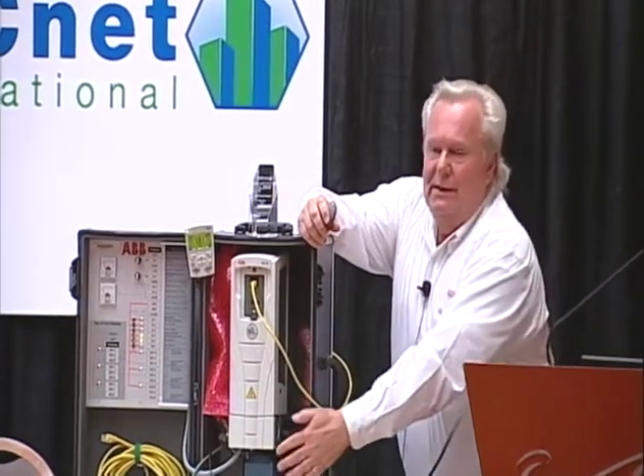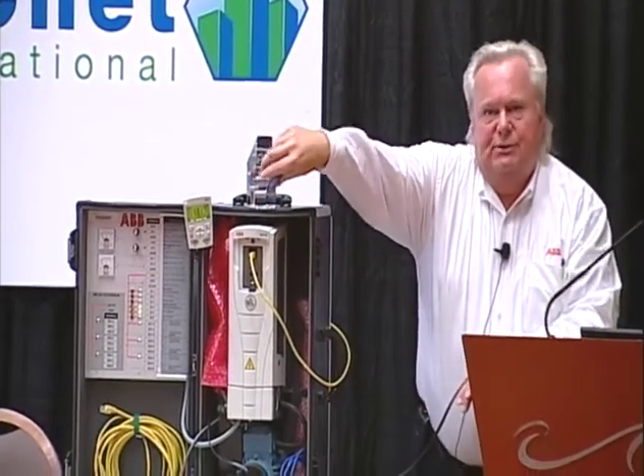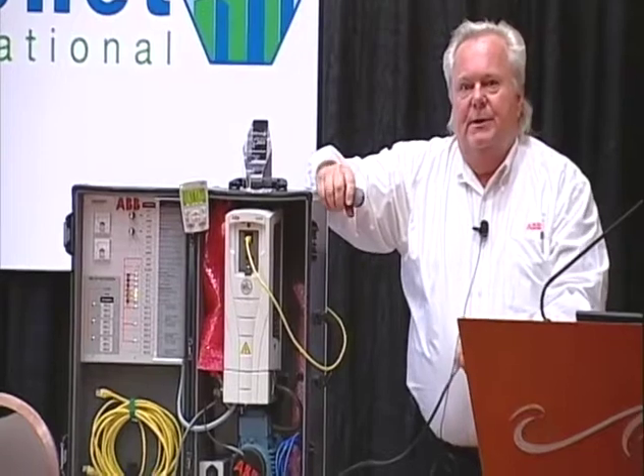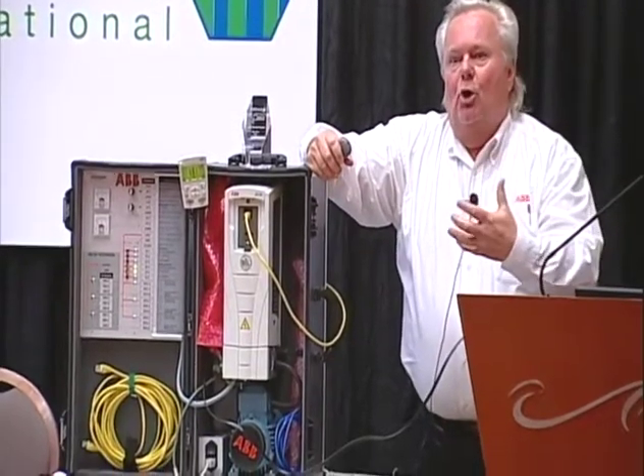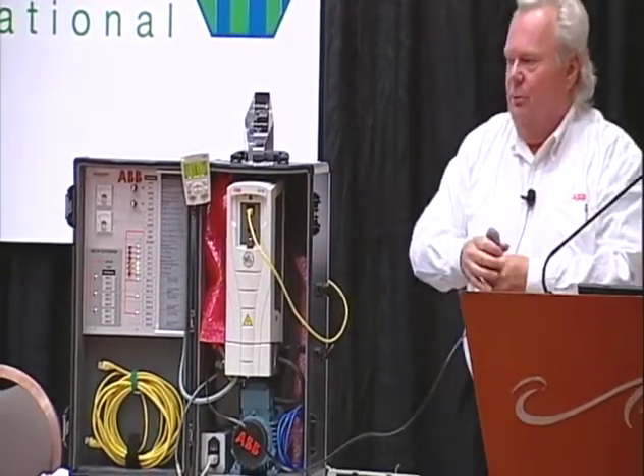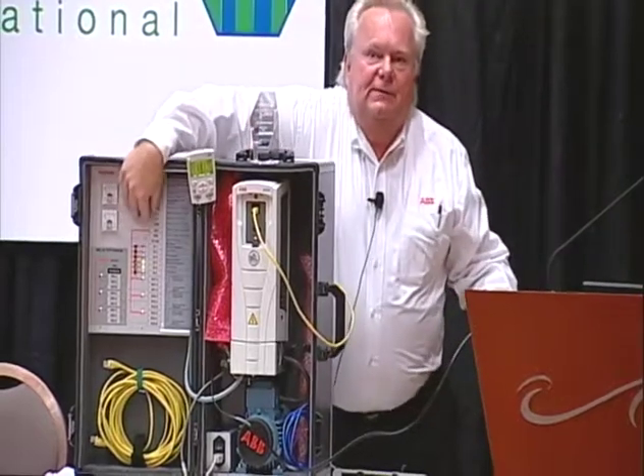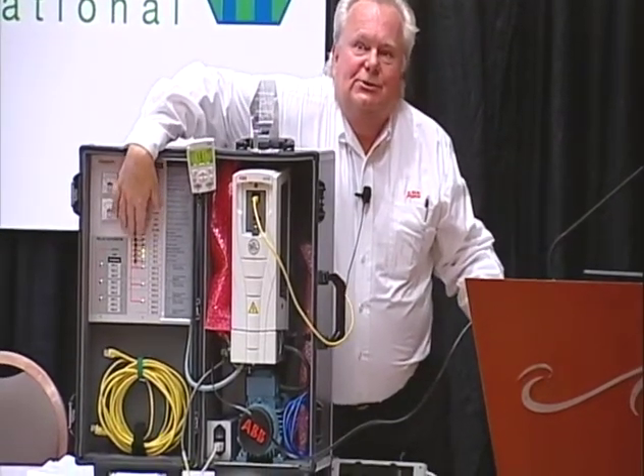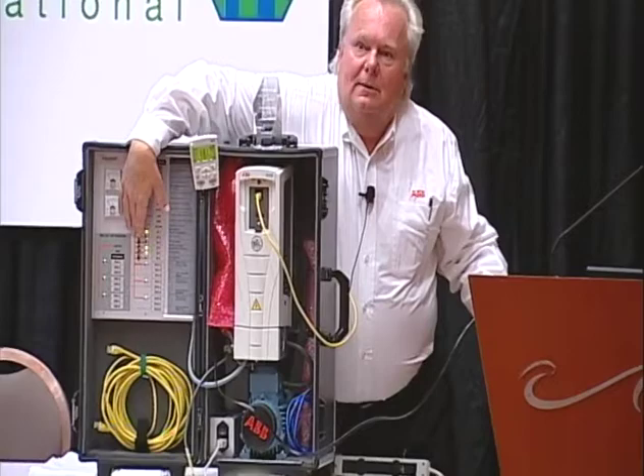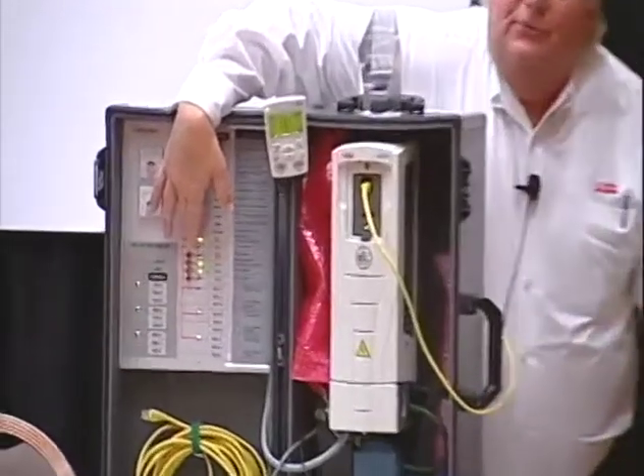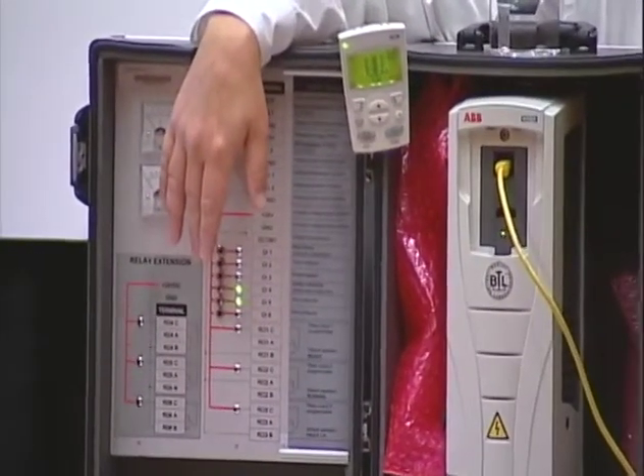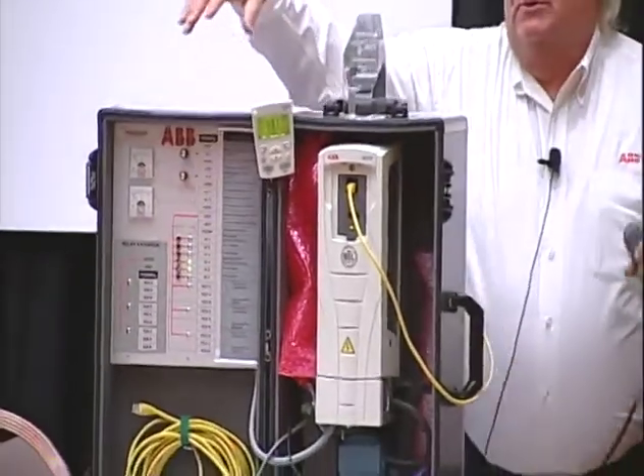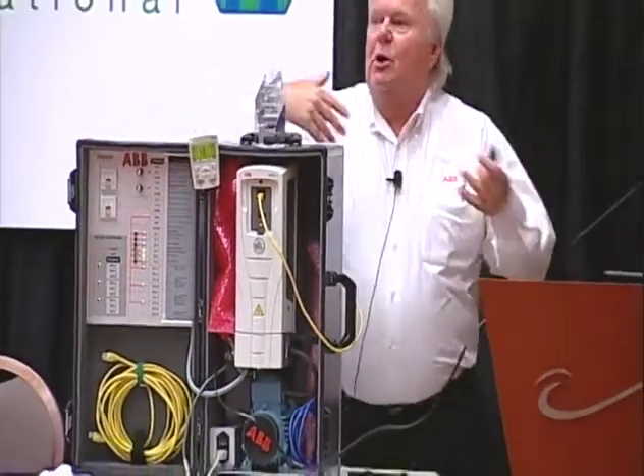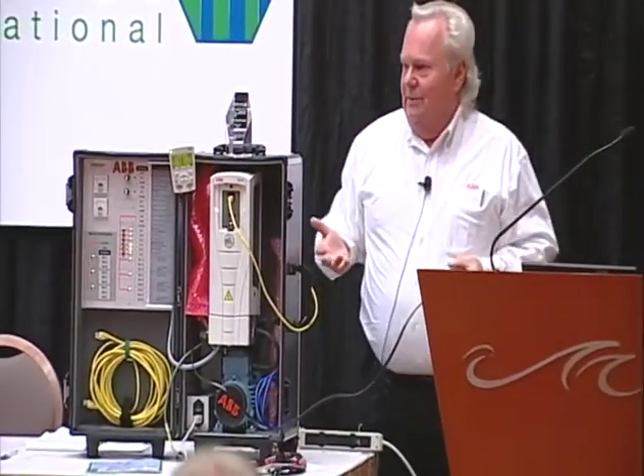So I got a little 1/8 horsepower 3-phase motor down here. On this side, I've got these switches and lights and meters that simulate the I/O from the real world. So in the old days, when you wanted to start this VFD, that contact closure would be wired to digital input 1. When that contact closed, that would tell the drive to start. Now I'm gonna do that over here. But this whole side over here is just all about demonstration. You wouldn't get that when you buy a drive, right?